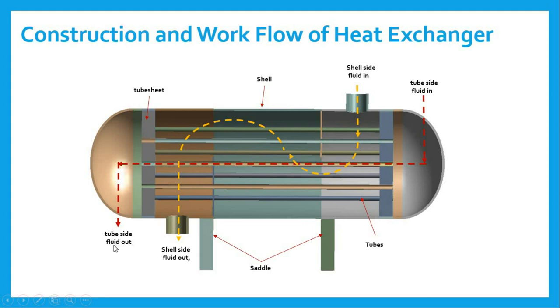The shell side region is where the fluid moves over the tubes. You can see the baffles here, which help maximize the heat transfer area. There may be different duty cycles — when the equipment starts and when it shuts down. In shell and tube heat exchangers, the equipment is subjected to thermal and pressure loads which may cause thermal fatigue due to high temperature cycles. Most stresses develop at the tube-to-tube-sheet junction and tube-to-shell junction due to high temperature gradient, as well as at the saddle supports.